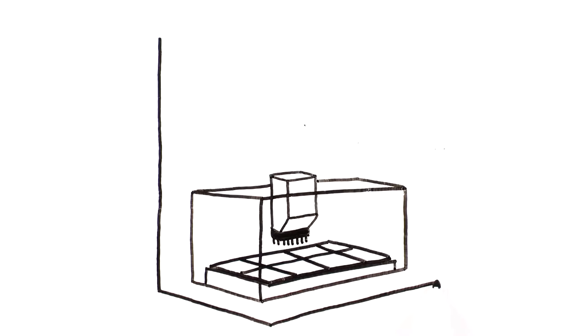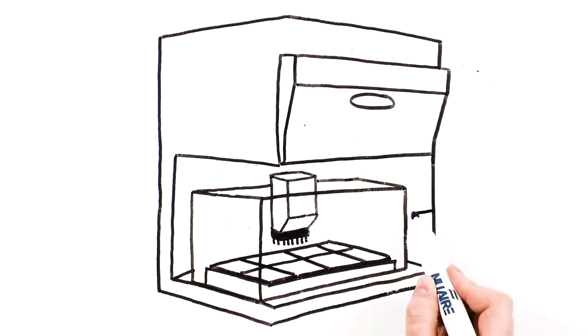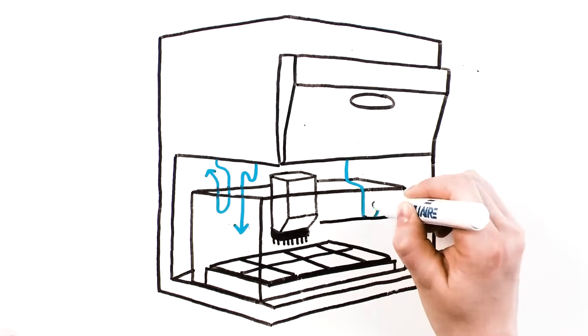The device may not physically fit inside a standard cabinet at all, or the fit may be so tight it prevents the proper air flows inside the cabinet from providing containment.